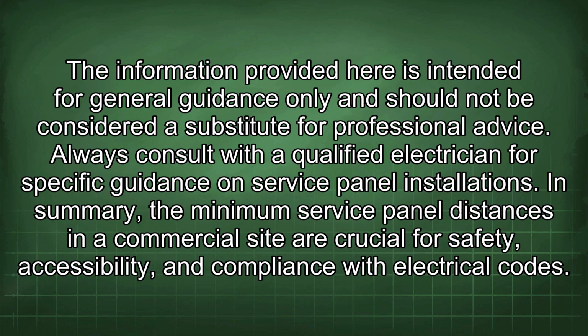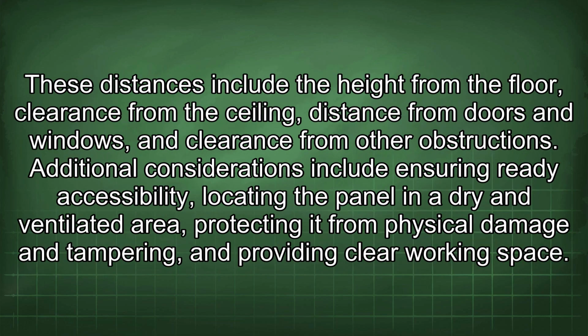In summary, the minimum service panel distances in a commercial site are crucial for safety, accessibility, and compliance with electrical codes. These distances include the height from the floor, clearance from the ceiling, distance from doors and windows, and clearance from other obstructions. Additional considerations include ensuring ready accessibility, locating the panel in a dry and ventilated area, protecting it from physical damage and tampering, and providing clear working space.